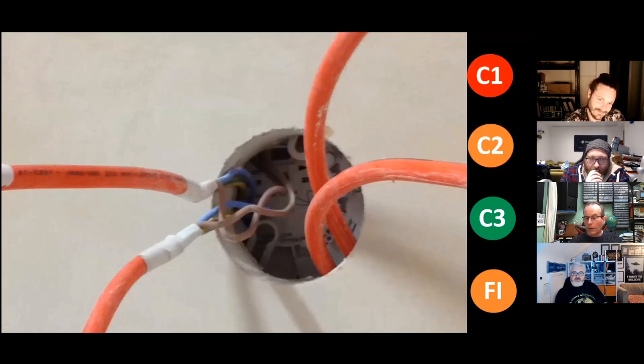Get C1 back. What the hell is this? Okay. So a bit of plasterboard. We're looking from above the ceiling downward. I'm assuming we're looking above the ceiling downwards, yeah. That's not really what I would expect to see for an FP cable going into a fire alarm. That's a bit bodgy, to be honest with you. Is that a word in 5839? Yeah, it's a bit bodgy.